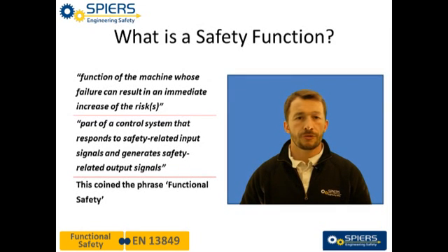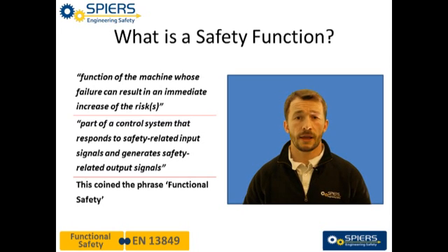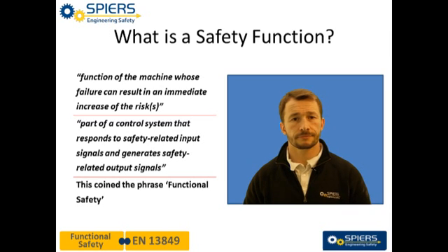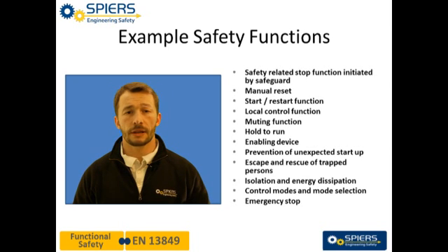During the design of a new machine or safety circuit we must identify all the safety functions. A safety function is any control system — electrical, pneumatic, or hydraulic — whose failure can result in an immediate increase of risk to an unacceptable level. There are a number of examples of safety functions given in EN 13849.